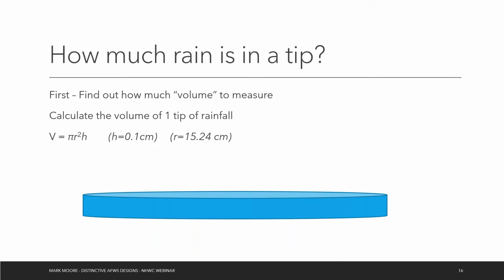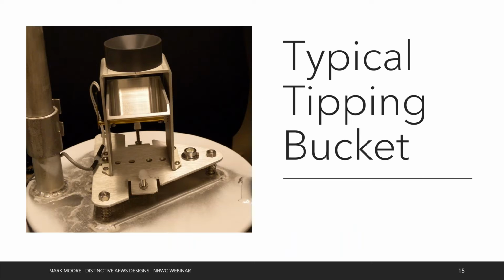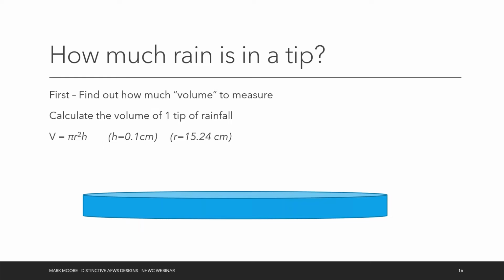But if you think about it, a tipping bucket is collecting a certain amount of rainfall, and that rainfall has a depth based on however much a single tip is. So say you have a tipping bucket that's 0.04 inches, which is what we've got right here on our bench and what we've got in this previous picture. This tipping bucket is actually a 1 millimeter tipping bucket, but it's often reported as 0.04 inches of rain. So that means for every 1 millimeter of rainfall, it's going to tip once.